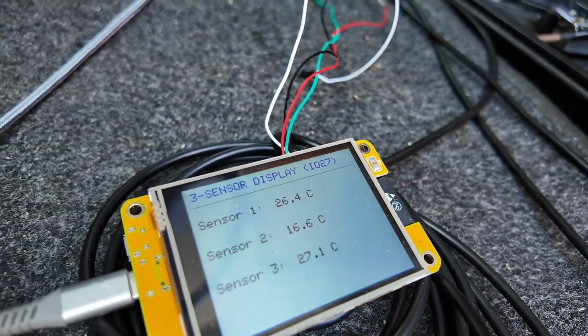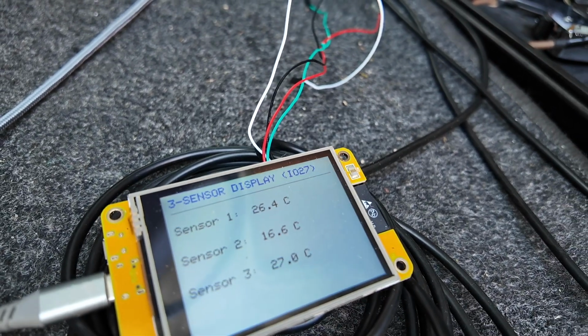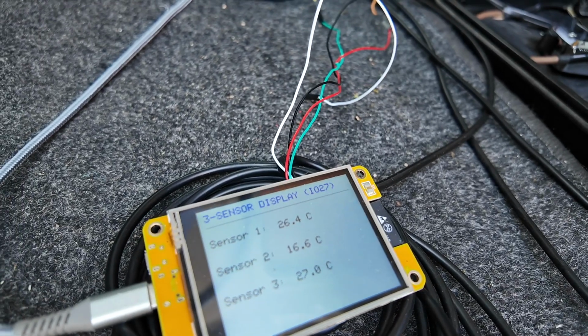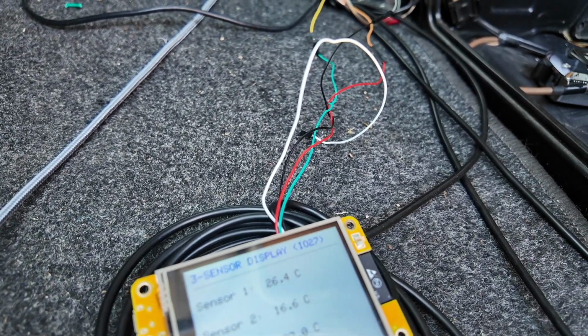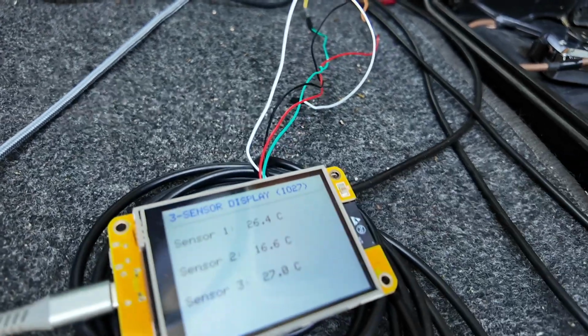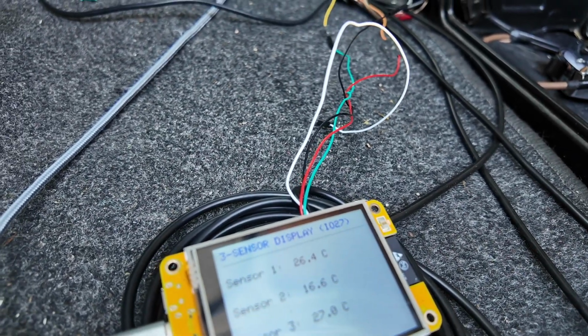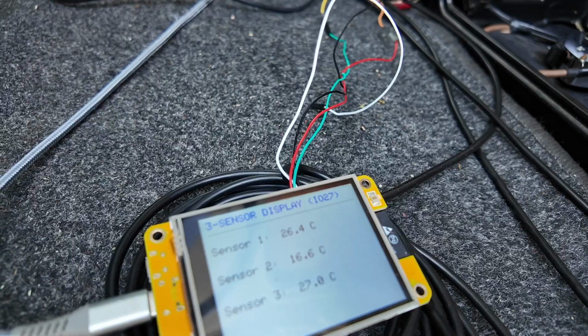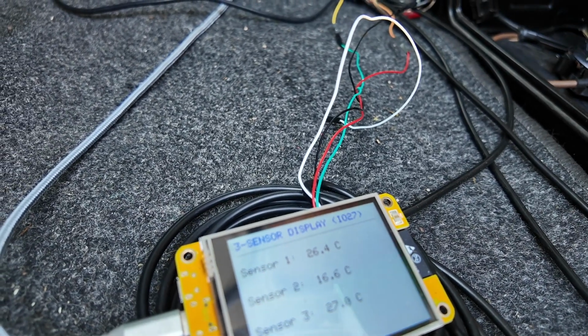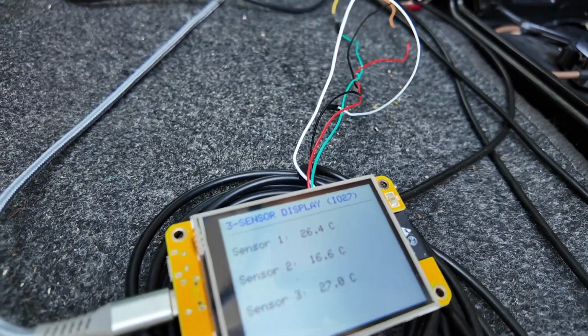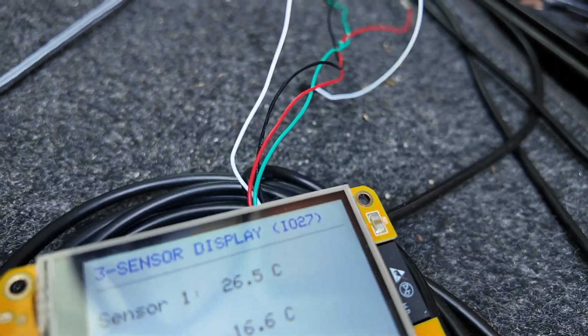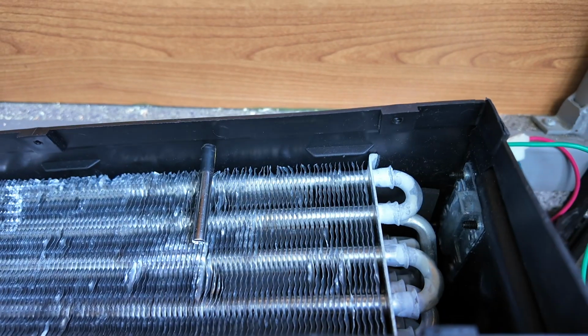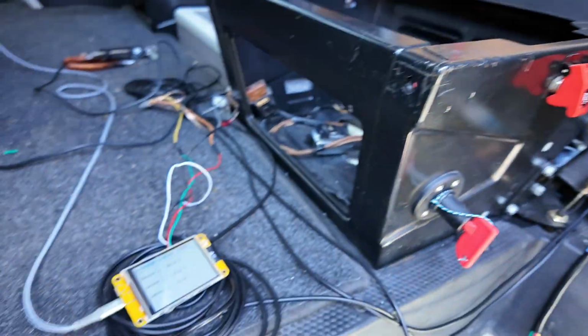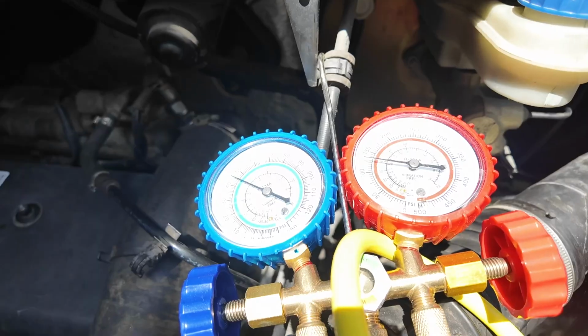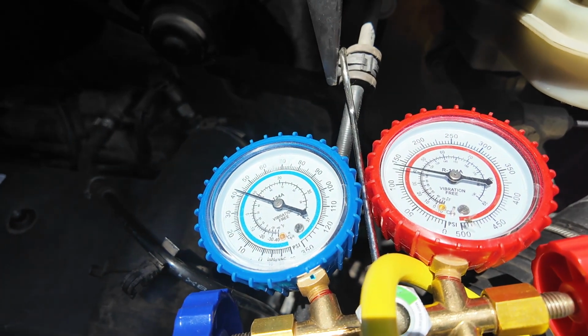So sensor 2 is in the bucket, 16.6 Celsius. That's the cool water, the 5 kg water. Sensor 1 was what? That's the evaporator outlet, the superheat. Number 1 is the evaporator outlet, and number 3 is this one in front of the evaporator, the air temperature. Okay, let's crank it up. Okay, system just kicked in.